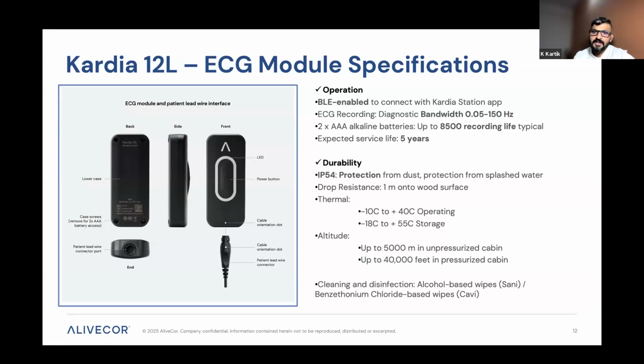The ECG recording bandwidth, which I think is also important, is around 0.05 to 150 Hertz. The module holds two alkaline batteries, which have the capacity for up to 8,500 recordings with just the two batteries, right? And the expected service life of the entire device is 5 odd years. Durability wise, it has gone through multiple required tests, be it protection from dust, protection from splashed water, or drop resistance.